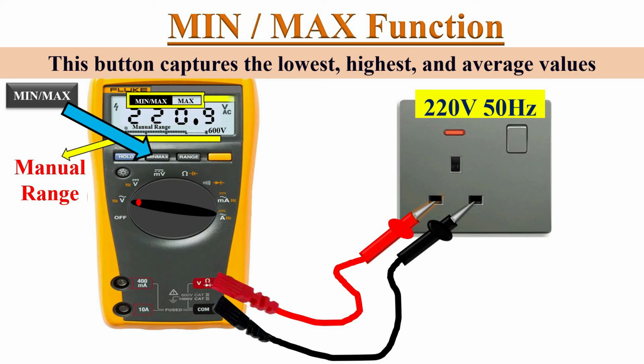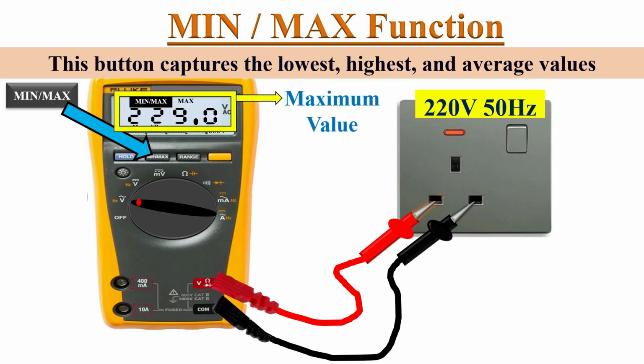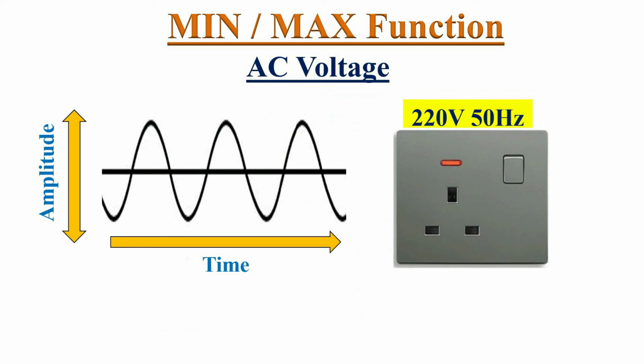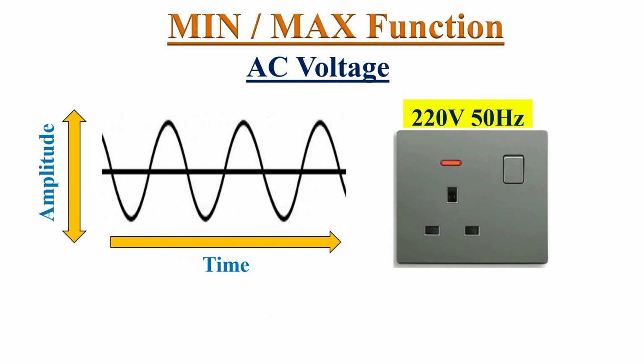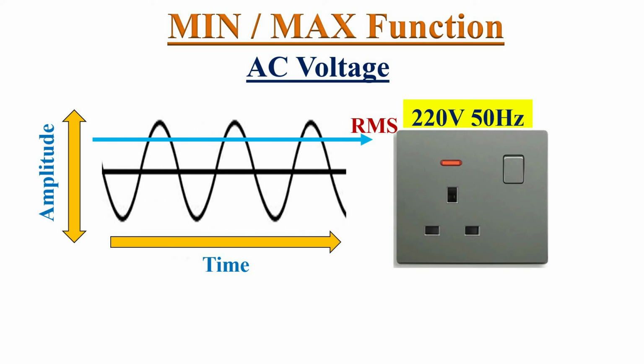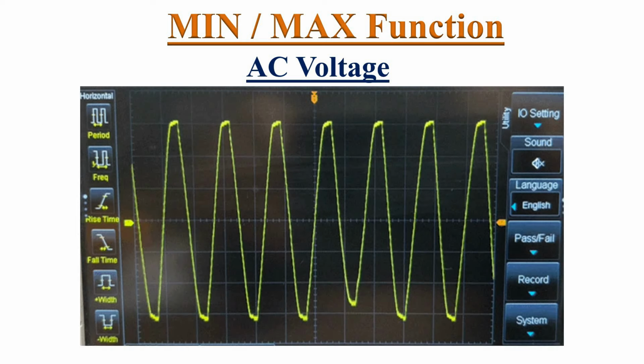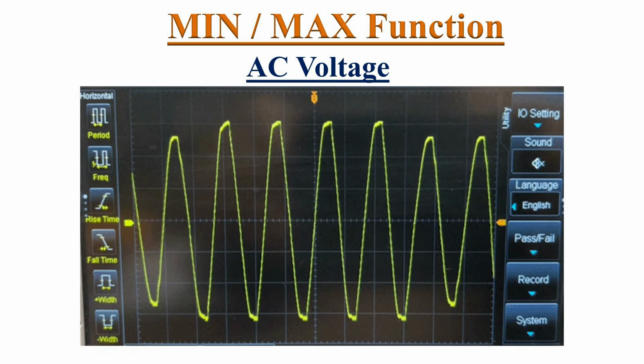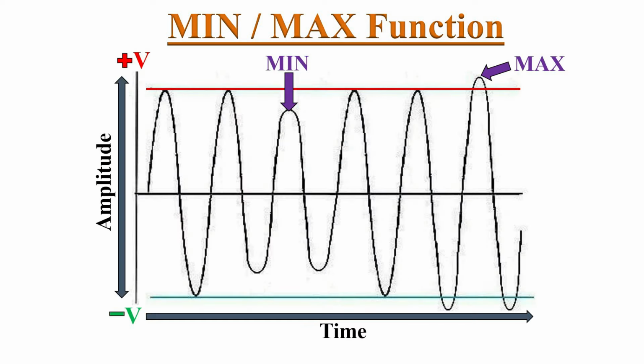The highlighted min-max and max characters show on the display. If we measure 220 volts, here the meter reads the maximum value of the measurement, that is 229 volts AC. Let's discuss what this function actually measures. As we know, alternating current varies with time and the multimeter measures the RMS value of these variations. If we observe these variations with an analyzer, we can see small variations in their peak values. Because of the variations in the peaks, the meter's RMS value measurement will also fluctuate.